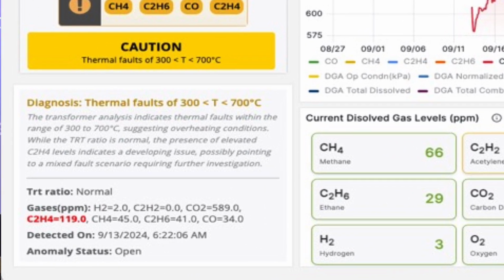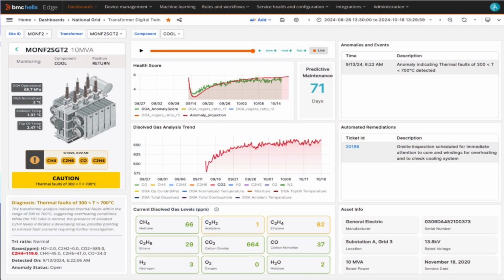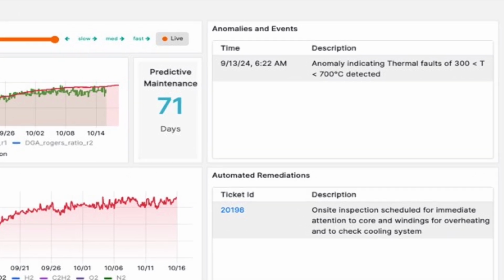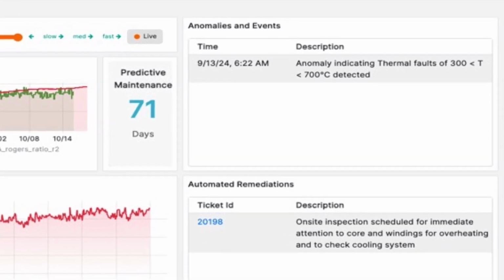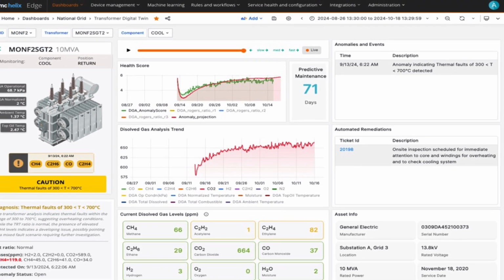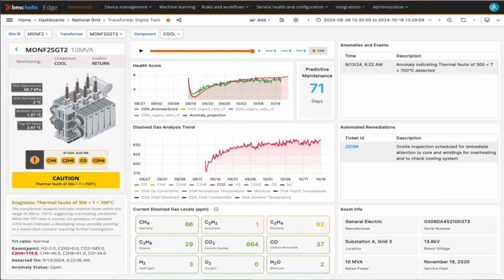And in this case, the anomaly was predicted, but then AI turned that information into a plain language assessment of what's actually happening and what you should do about it. That information then has a human decide what they want to do, or because you can orchestrate into other systems like maintenance systems, that information can immediately become a service ticket in a service management system, and it's not just an alert. Now all of a sudden we're starting to take action on that information. So we've gone from just seeing our transformer to understanding and predicting what's going to happen with this transformer, turning that into information that can be used by a real human, then running it through automations to create all of the processes for service management tickets that turn this into some form of action.